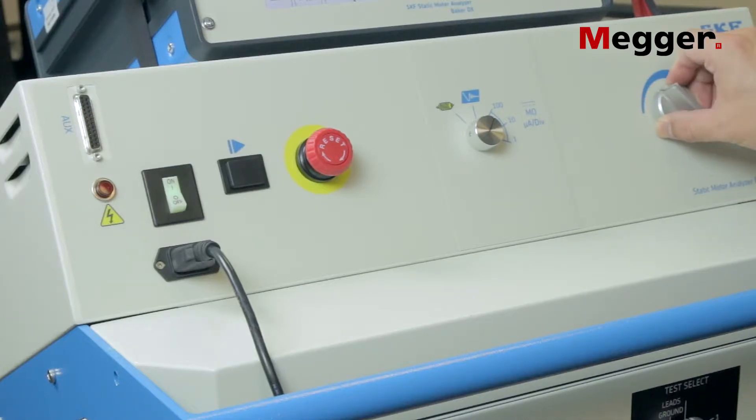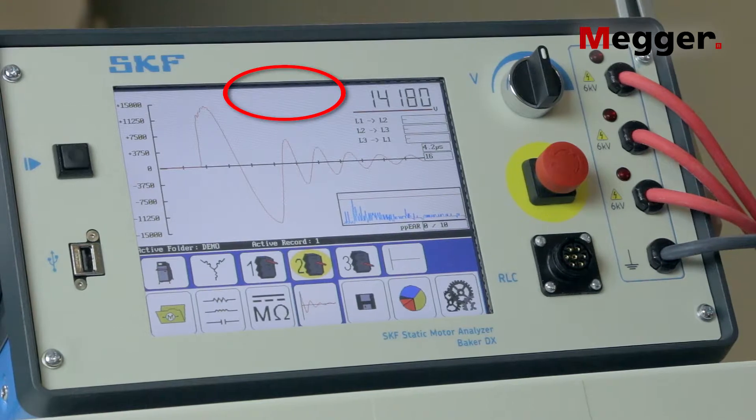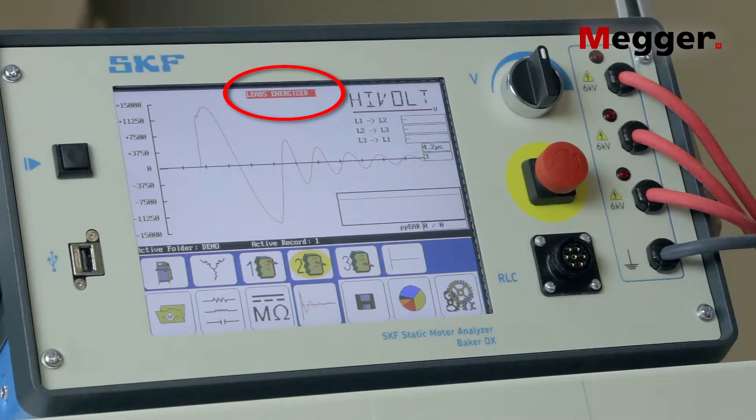Verify that the voltage control knob is set to zero. As a safety feature, any time the test leads are connected to the high voltage power supply, the warning lamps on the power pack will light up and the words leads energized will appear on the DX's screen.